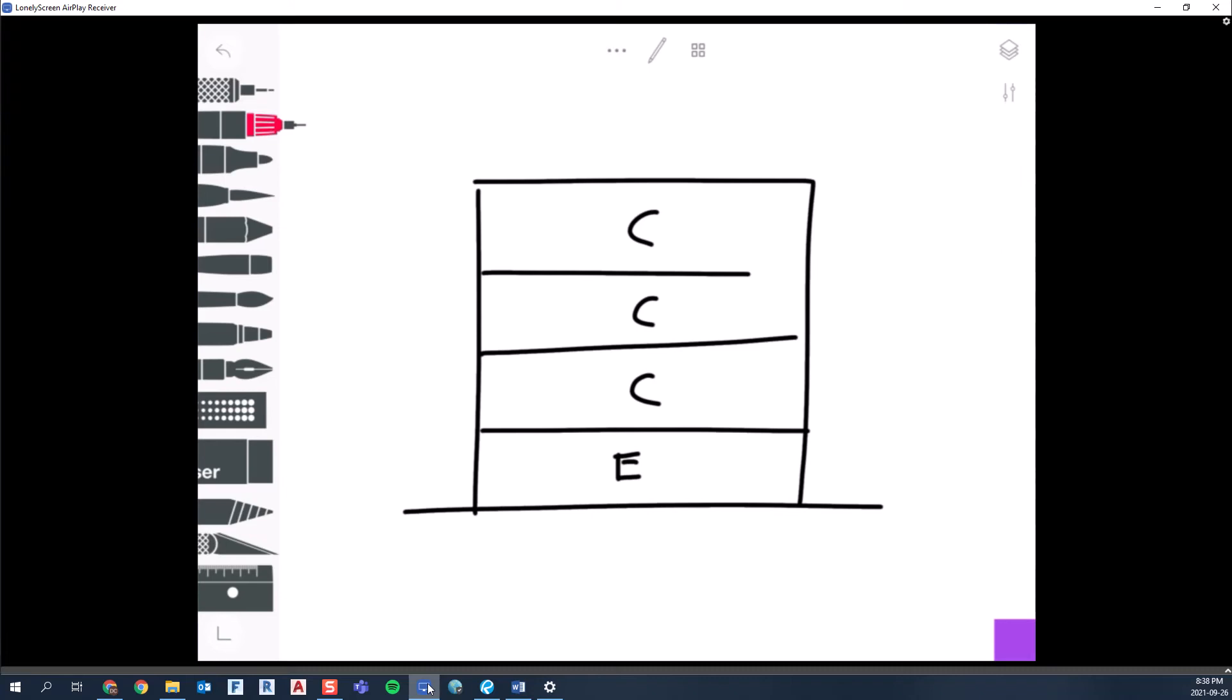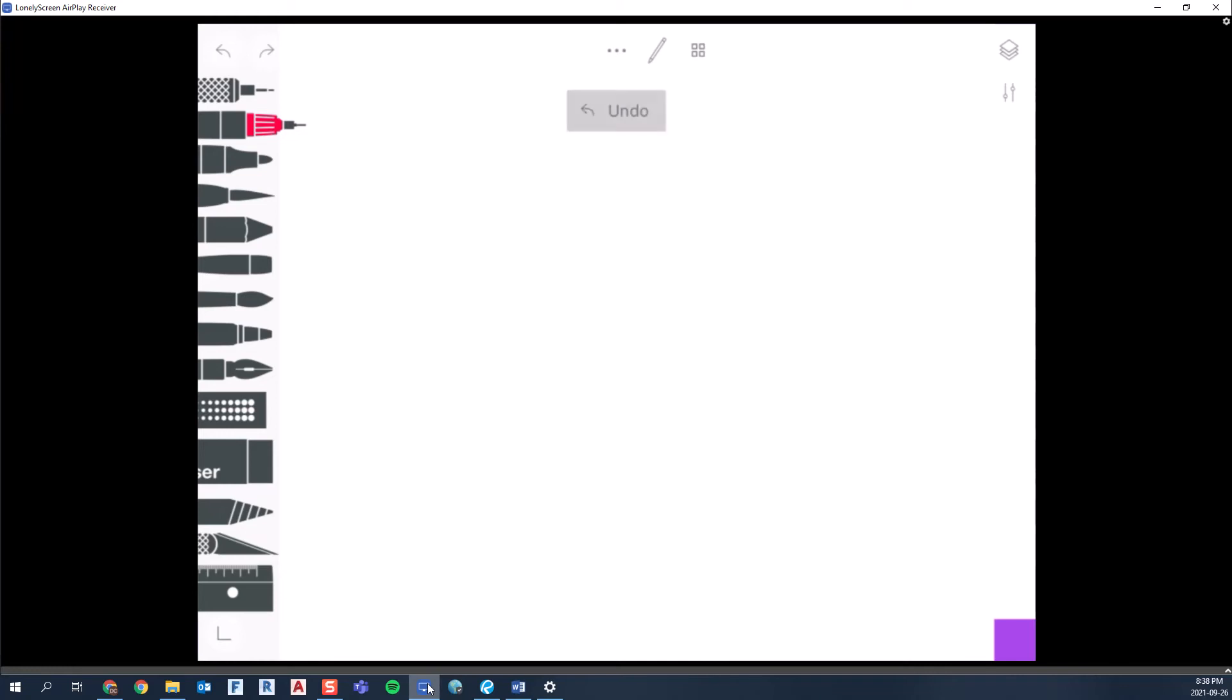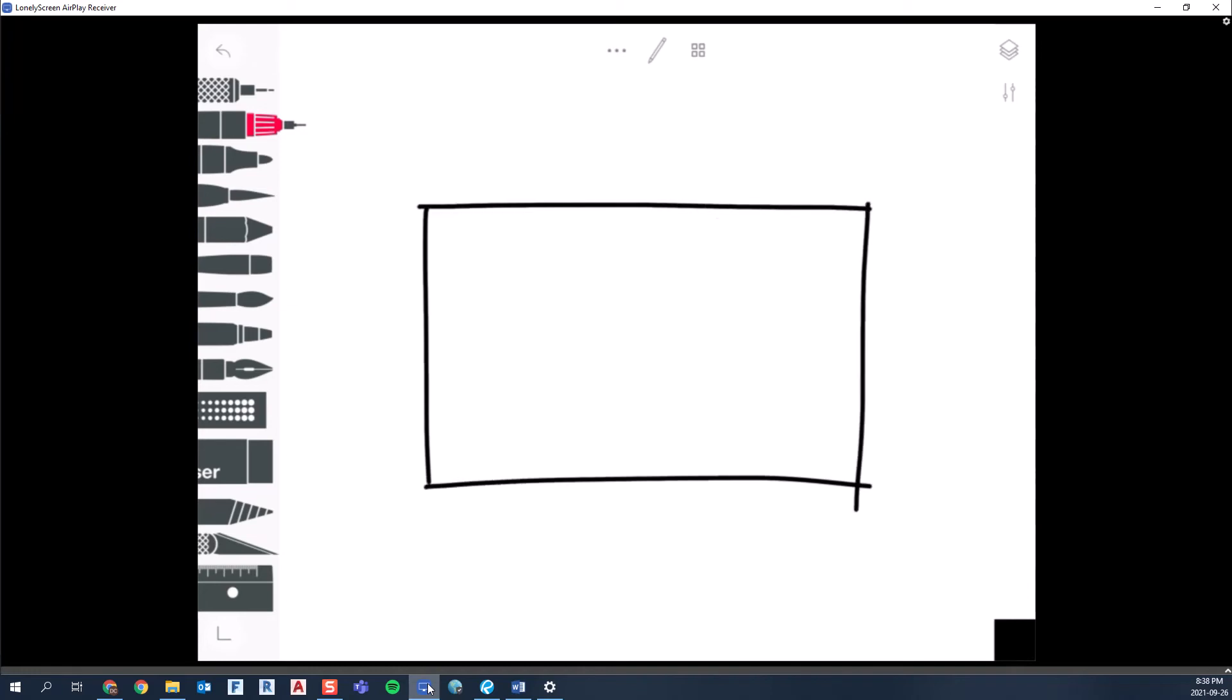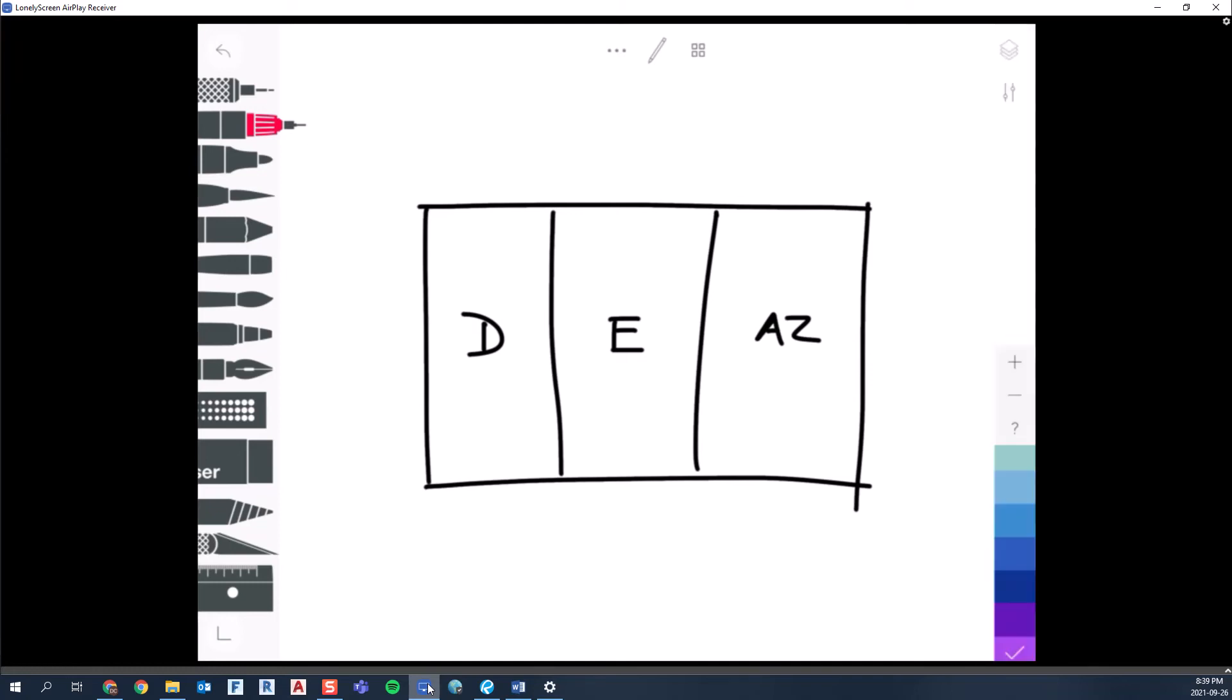Likewise, if we look at a building in plan view, like a strip mall situation maybe. And maybe there's three units in there. And let's just say the end unit is a restaurant. So that would be an A2. A retail space would be an E and maybe the end one's a dentist. So a D use. So the major occupancies in that building are A2, E, and D. And that's what that chart is for. It's just telling you right off the bat, okay, well, if you have a group E beside a A2, then right away, we can see that those major occupancies have to be separated by a two-hour fire separation. So that's really all that is.